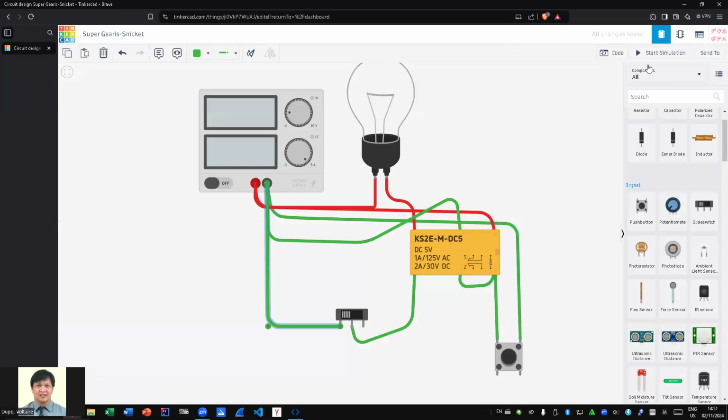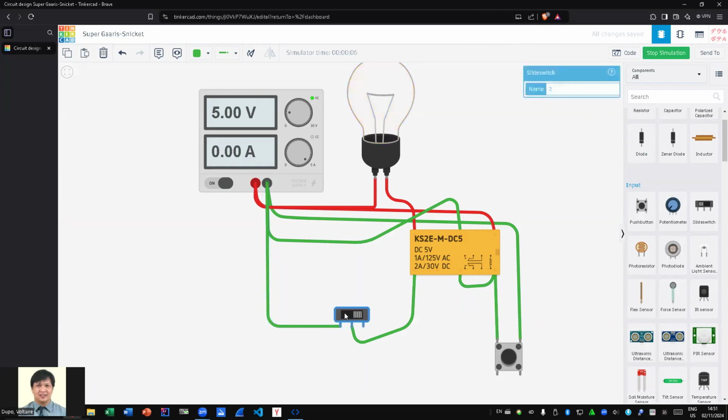When we look at the circuitry, you see that it's basically normally closed yung portion na yun. So hence, when we start the simulation and press this one, it's latched. If we click this one off, we disrupt the flow of current going into the coil, and we basically are able to terminate the connection point. Okay. So this is a latching control circuitry.